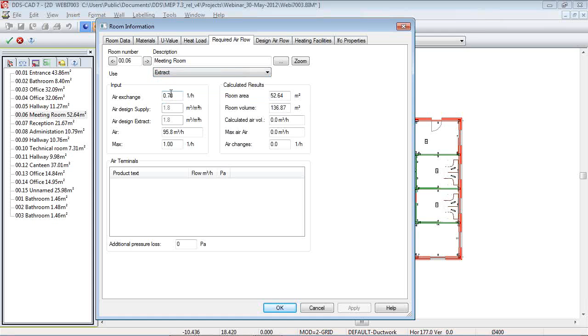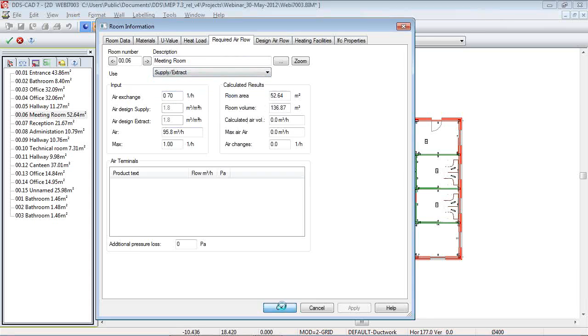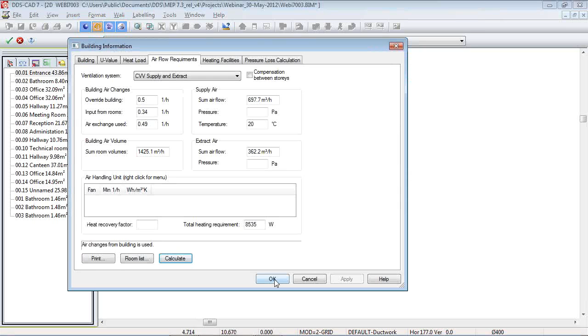This kind of information can be added from our experience. When it's not correct, or the room function changes, we can easily change from supply-extract to supply only, and for a bathroom we can set it to extract only. The information can be changed very rapidly, and we're still able to do recalculations. Looking at this room, we see no air is needed because no room settings requirement was set. When we rerun the calculation with a new setting for this room, we get a message about balancing, and after repaint we see 96 cubic meters an hour is needed in this room - this is reuse of the information, like designing and adding information.